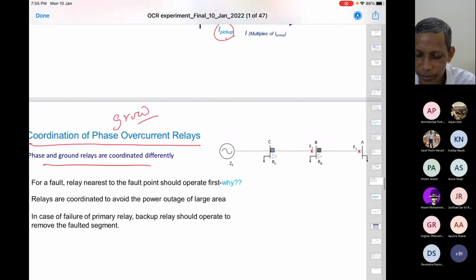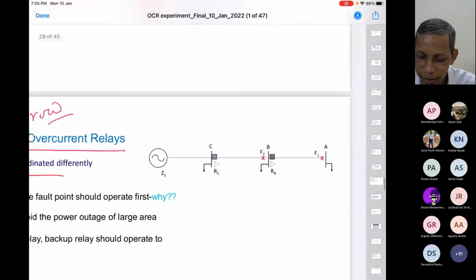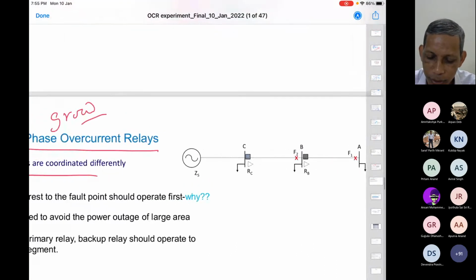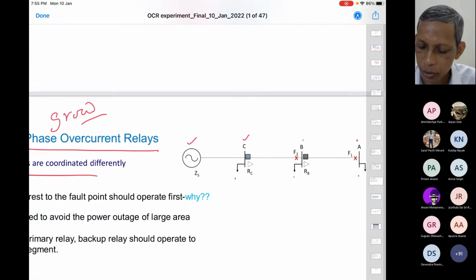What is coordination? Try to understand that. Let us say this is the system source. We have a bus where load is connected, another bus with load connected, and another bus with load connected. High voltage, low voltage, whatever system may be there. In this arrangement, we essentially require two relays. Let us say at bus B we have relay RB, and at bus C we have relay RC. Think about a fault at F1.